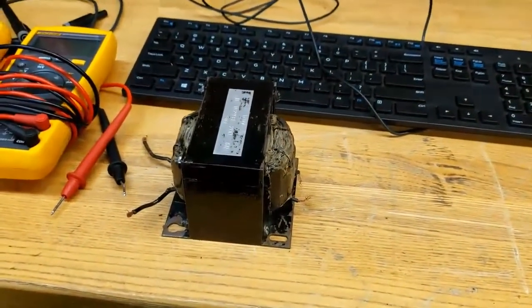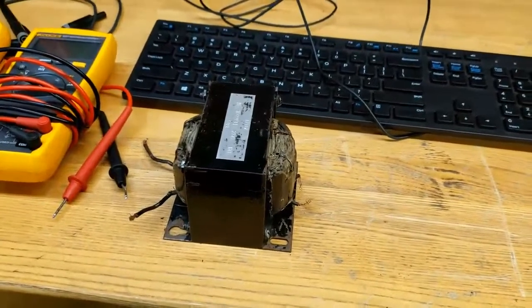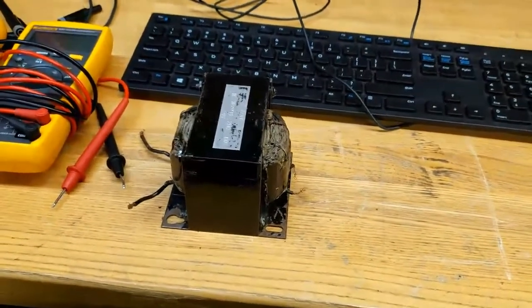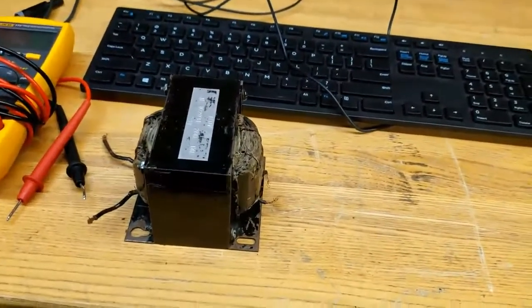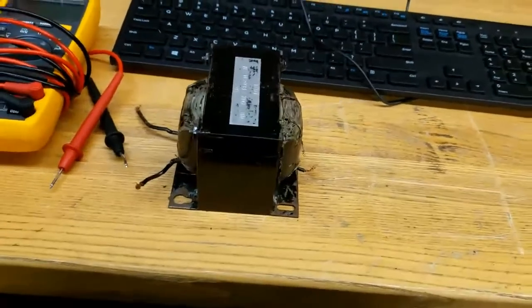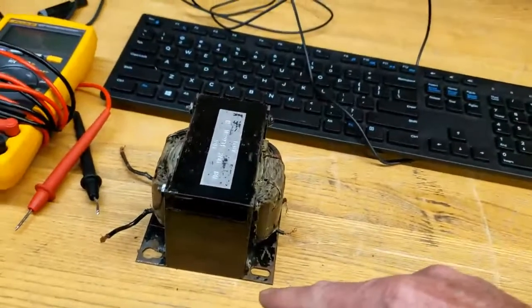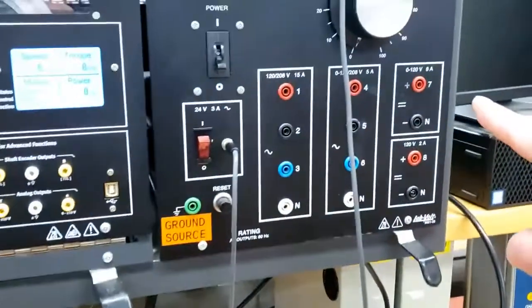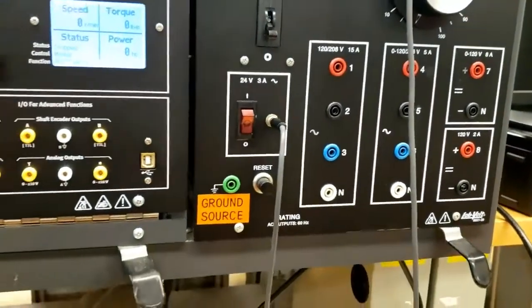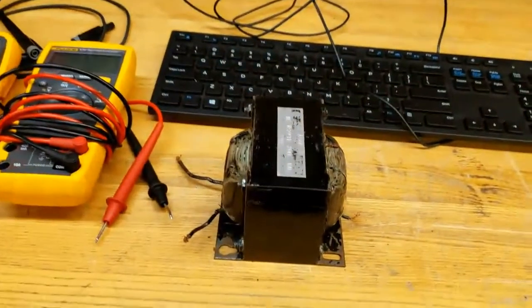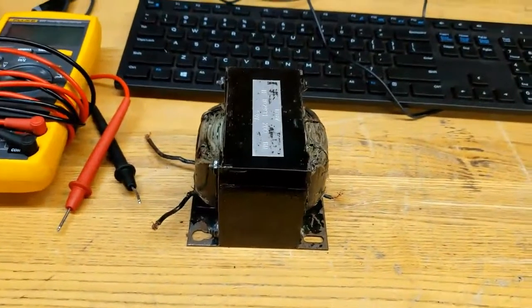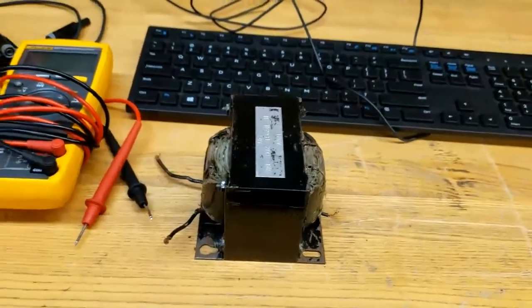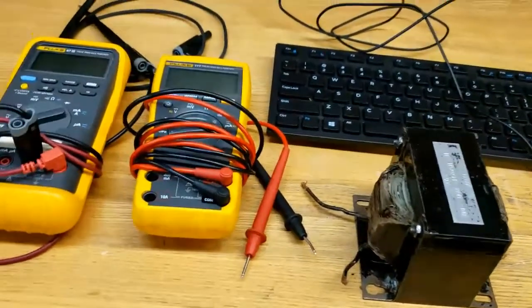You'll be running a line from the power supply, positive, through the ammeter, and take your lowest reading on the transformer. If it was low to ground or high to ground, pick one of those and connect the voltage to that, and the return line on the ground or on one of the terminals will then go back to your negative. So you have a series circuit, 33 volts through the ammeter, through the transformer and back, and you should be getting current in the microamps.